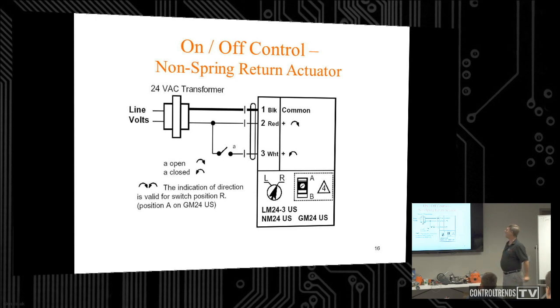Now as far as the wiring goes, go by the instructions for whatever actuator you have. On this particular actuator, we've got 2 wires landed on power, and this thing is going to tend to rotate clockwise unless you put power on terminal 3. So you've got common on 1, power on 2, and you're making and breaking power on 3. Without power on 3, you're going to rotate clockwise. If you apply power on 3, it overrides it and drives it counterclockwise. That's a little bit odd, I just want you to be aware.